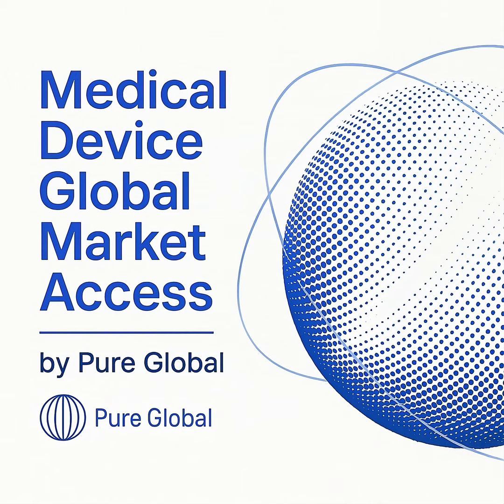Third, conduct a gap analysis of your technical documentation against the new special controls. Pay special attention to your software validation evidence and labeling to ensure they meet the heightened requirements for transparency and performance reporting. This new classification by the FDA represents a major step forward in regulating AI medical devices, offering a clear pathway that encourages both innovation and safety. By understanding the requirements for the device classification, the special controls, and the critical role of the Predetermined Change Control Plan, manufacturers can better navigate the regulatory landscape and bring advanced imaging tools to market more effectively.